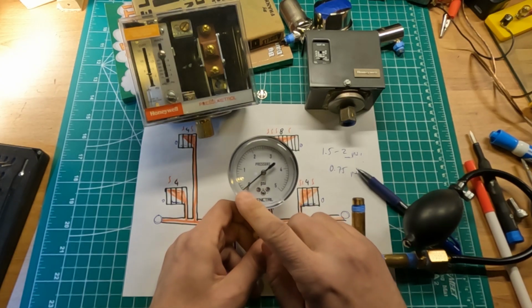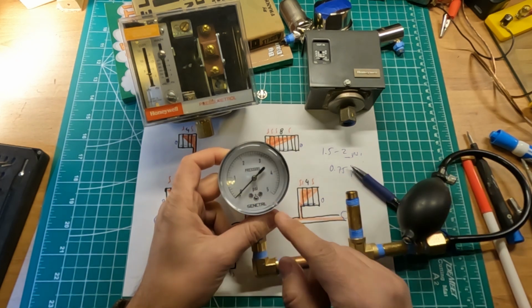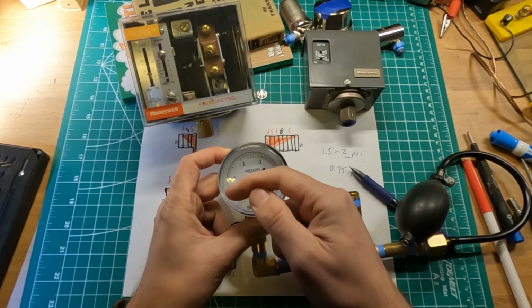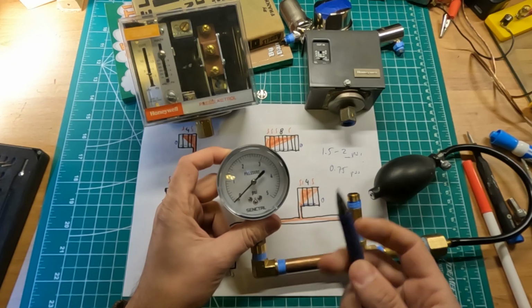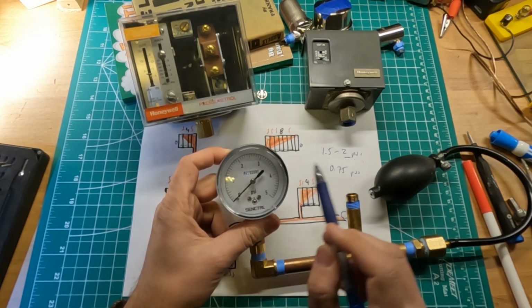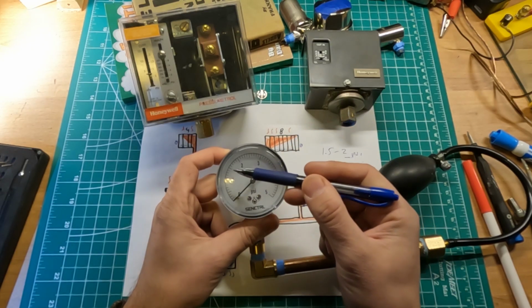So this is 0 to 5 psi. Most boilers have code-required gauges that go from 0 to 30 psi, which means you would barely see any movement on the scale. Meanwhile, on this one, 0 to 5, if you have your Pressuretrol correctly set to, let's say, shut down the boiler at 1.5 psi, then of course it's going to slowly rise to 1.5 psi.